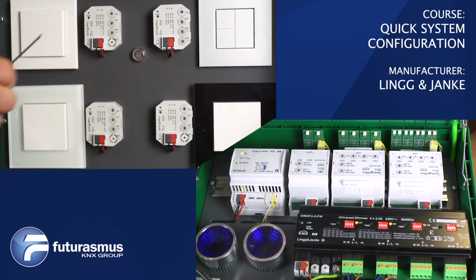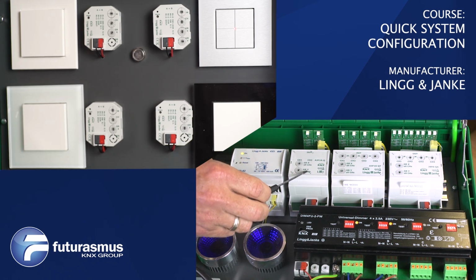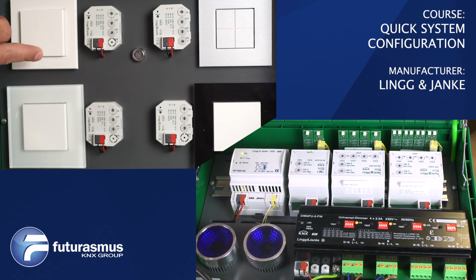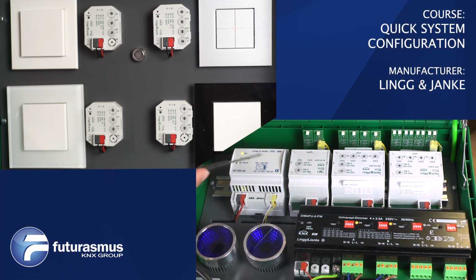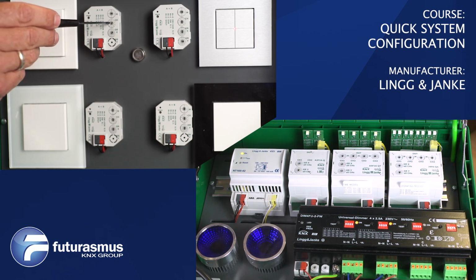Now let's say the customer says afterwards he wants to program and he puts another light, he puts another actuator on it. Let's say he connects this actuator and he wants to switch on and off this channel 2, for instance, with the same push button. So let's see how easy it is. You only go to the actuator, you set the X to the number 2, because the X channel is number 2, and then you will set.